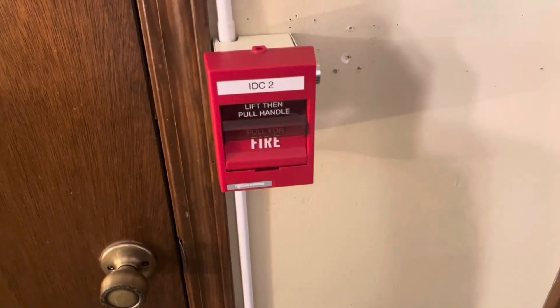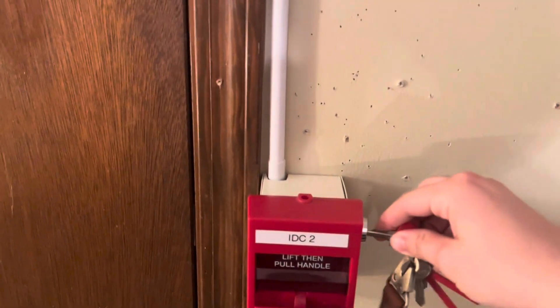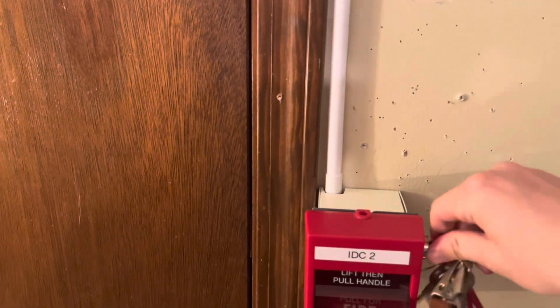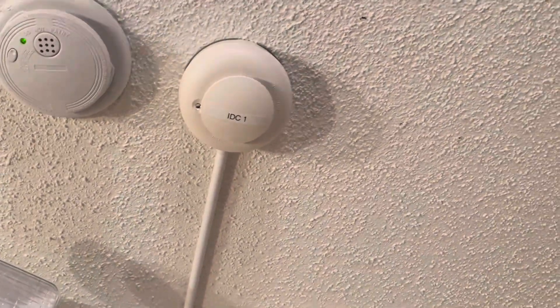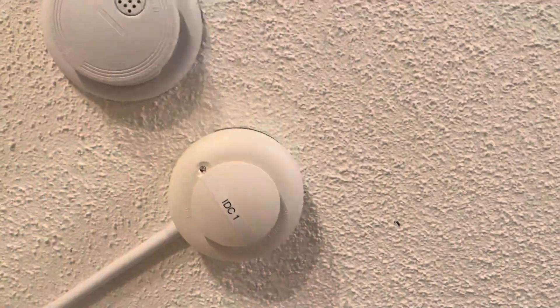I'm going to go ahead and do the other pull station while I still can. I'm at the other pull station and we're going to pull it. Now it's the pull stations on IDC 2, and this smoke detector is on IDC 1 — I guess I'll go ahead and do this one too. There we go, it's going to go off.